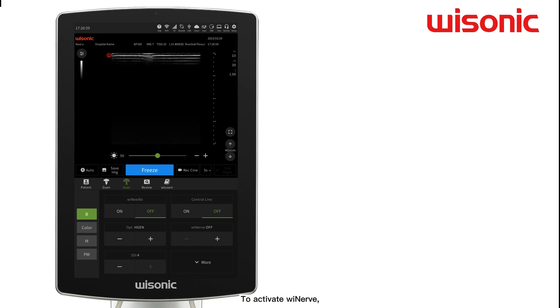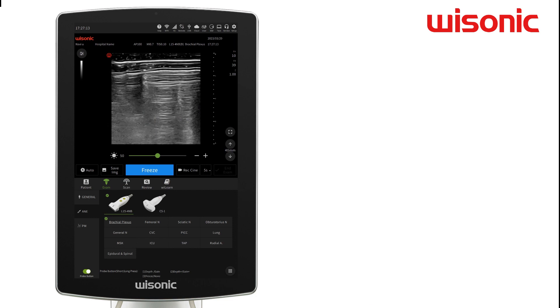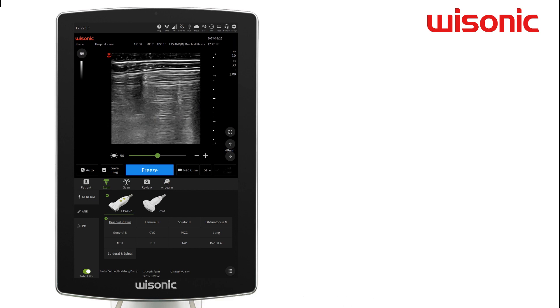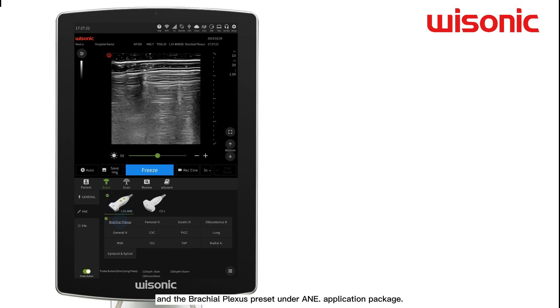To activate wiNerve, select the specific transducer and preset first. For example, to get access to the Brachial Plexus approach, select the linear array probe and the Brachial Plexus preset under the Anesthesia Application package.